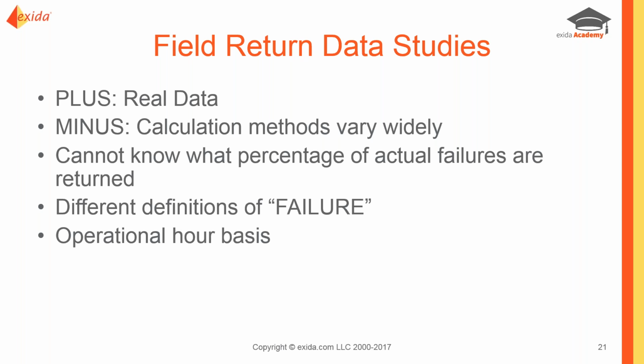shortage in the information. And there are different definitions of failure, as I pointed out on that previous slide. When the calculations are being done, it's important to have the operational hours match up to the actual sample set, and sometimes we will see that the operational hours are based on shipping records. So if only some of the failures are being counted for when devices are returned, and others are just being thrown away without the return data reflecting what happened, but the operational hours are based on all shipping, that can again lead to a very low failure rate coming out of this kind of study if it's not adjusted for the ones that are not being returned.